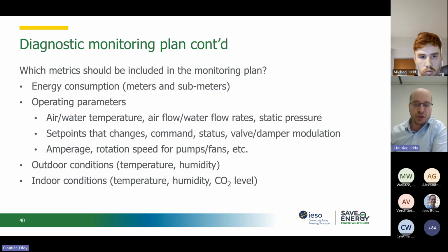Other elements which are very generally included in monitoring would be water and air temperature, water or air flow rate when available. It's not always the case. Static pressure, set points which change according to programming, controls such as on-off on pumps, fans, and so on. Valves and dampers modulation, motor amperage, etc. So there's a lot of information that can be obtained by the BAS system.